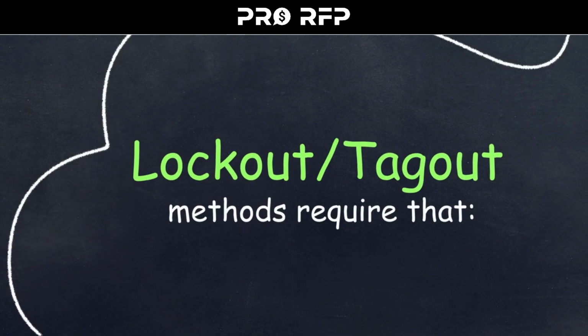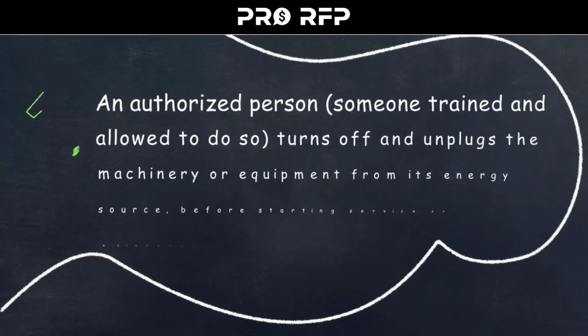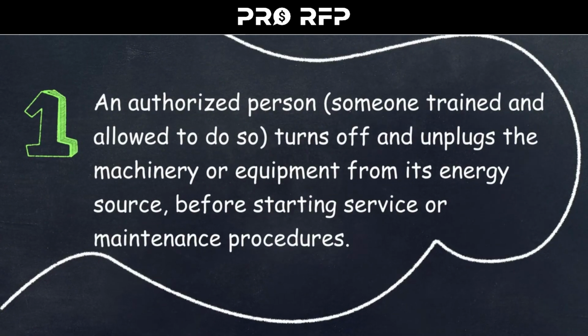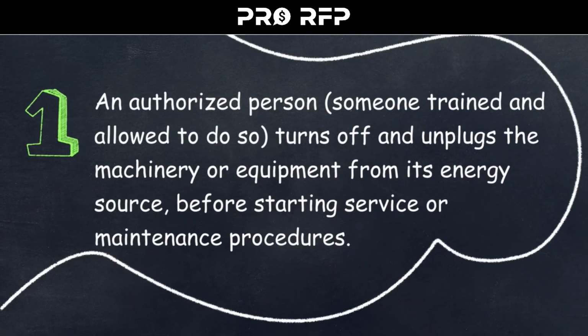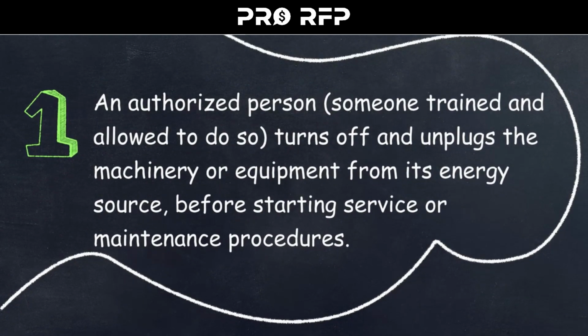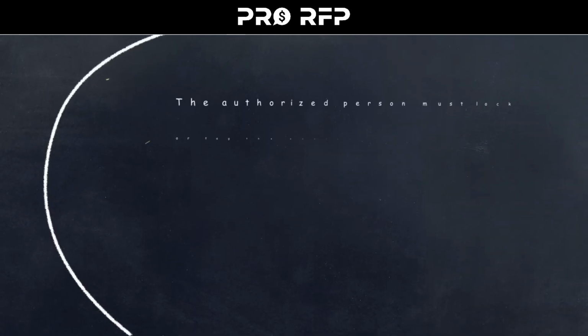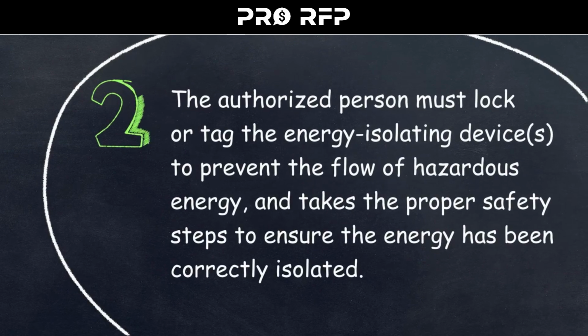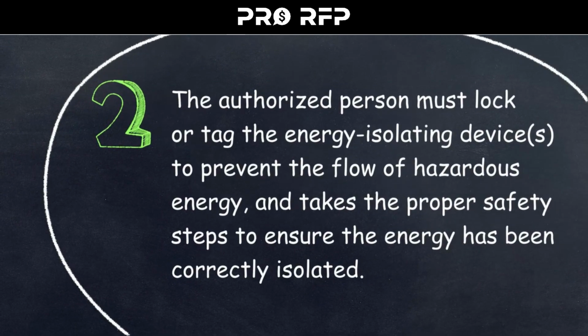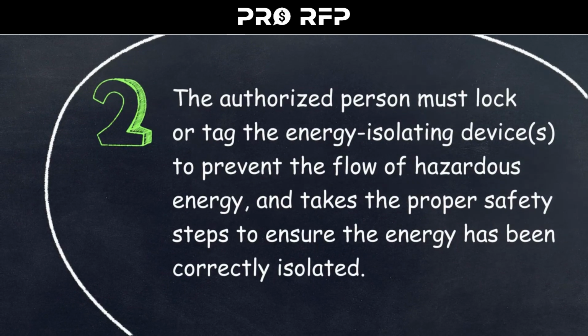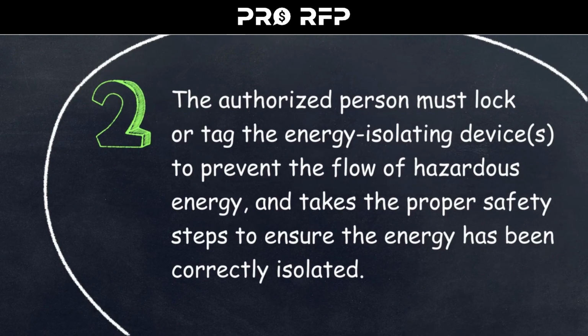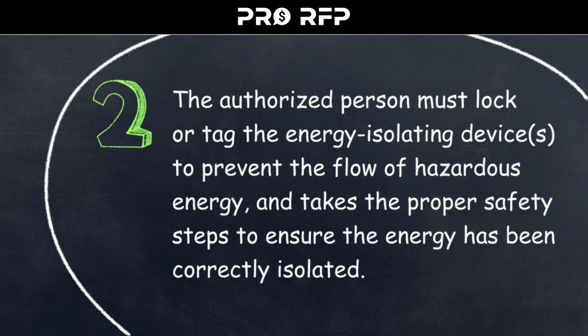Lockout-tagout methods require that an authorized person, someone trained and allowed to do so, turns off and unplugs the machinery or equipment from its energy source before starting service or maintenance procedures. The authorized person must lock or tag the energy isolating device to prevent the flow of hazardous energy and takes the proper safety steps to ensure the energy has been correctly isolated.